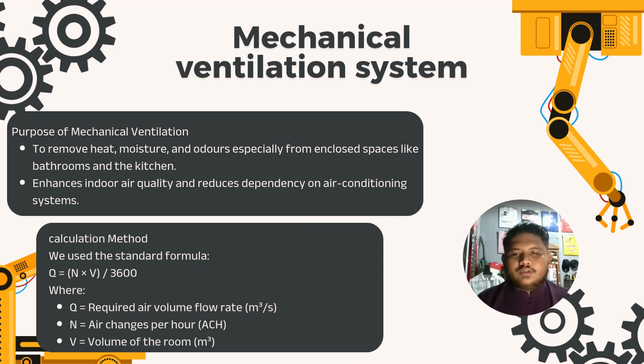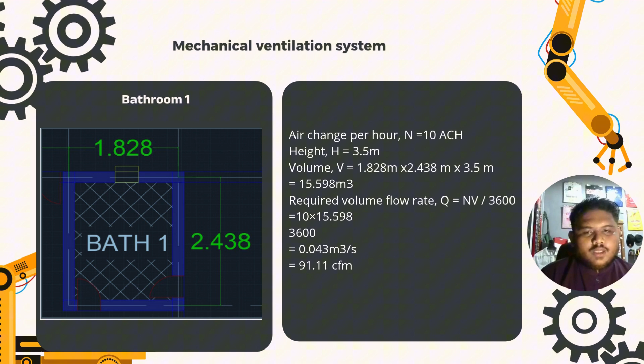First, the mechanical ventilation system for the bathroom. Air change per hour equals 10 ACH. Height is 3.5 meters and volume is 15.598 cubic meters. Required volume flow rate Q equals ACH times V divided by 3600, and we get 0.043 cubic meters per second. After that, we need to convert to CFM, so we get 91.11.